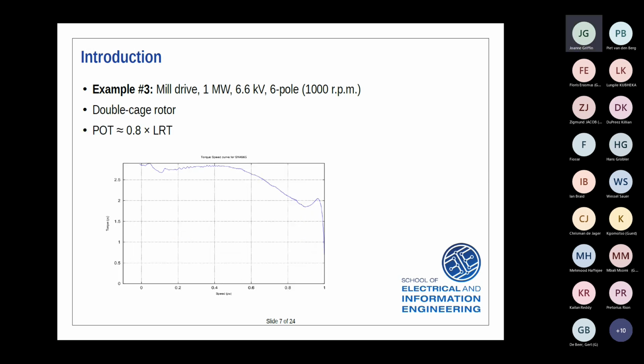Right, in the next case, this is a classic mill drive torque speed curve, and always a double cage design. Here you can see the deeper cage contribution is dominating, and the original shallow cage, you can still see that impact. There's another curve over there. Here the pull-out torque is actually less than the locked rotor torque, about 0.8. So that's a classic mill drive. You can see very high torque values across the full speed range, which is what you want for a mill drive.